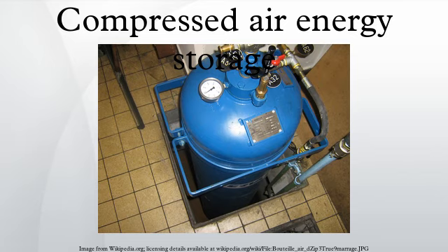This heat removal can be achieved by heat exchangers between subsequent stages in the compressor. To avoid wasted energy, the intercoolers must be optimized for high heat transfer and low pressure drop. Naturally, this is only an approximation to an isothermal compression, since the heating and compression occur in discrete phases. Some smaller compressors can approximate isothermal compression even without intercooling, due to the relatively high ratio of surface area to volume of the compression chamber and a resulting improvement in heat dissipation from the compressor body itself.